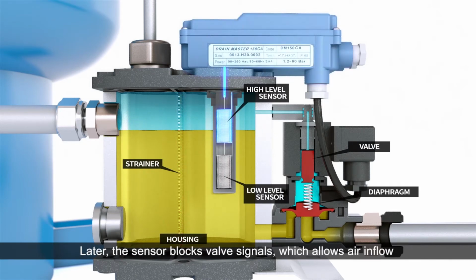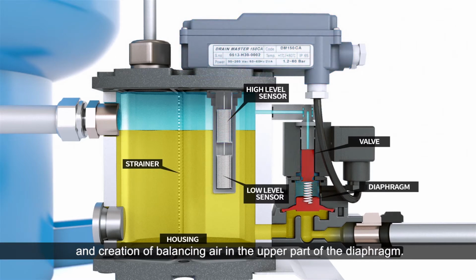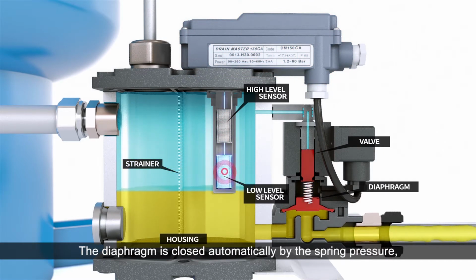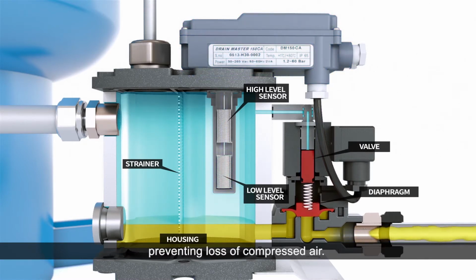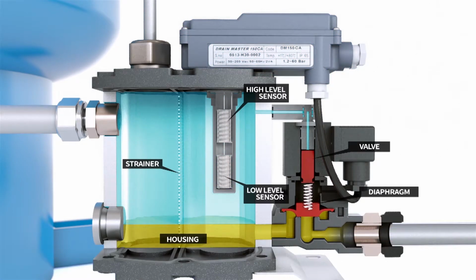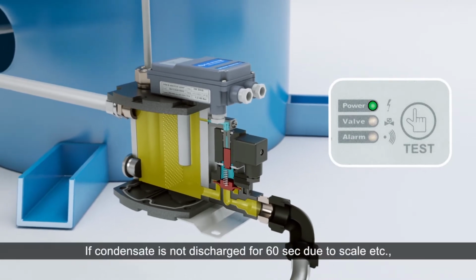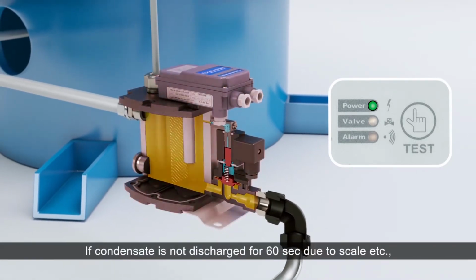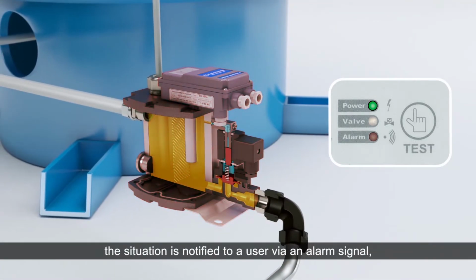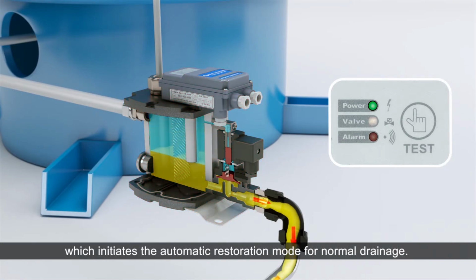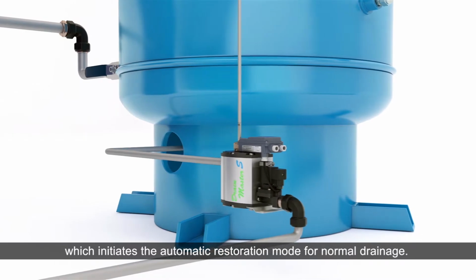Later, the sensor blocks valve signals, which allows air inflow and creation of balancing air in the upper part of the diaphragm. The diaphragm is closed automatically by the spring pressure, preventing loss of compressed air. If condensate is not discharged for 60 seconds due to scale, etc., the situation is notified to a user via an alarm signal, which initiates the automatic restoration mode for normal drainage.